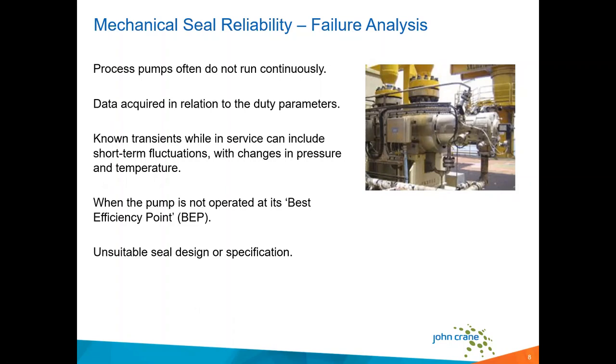Vibration is certainly a big factor when we look at mechanical seals. It can occur due to impeller wear, or operating the pump outside of optimum design efficiency, or outside of the BEP, the best efficiency point on the performance curve. Certainly this could cause problems with the seals and the bearings as well, especially if you look at the age of your equipment. If it's an older pre-eighth edition API pump, there are potentially some magnified issues with operation far left or far right of BEP in terms of hydraulically induced issues, shaft deflections and other issues. So vibration, tying back into operation of the equipment, operational data really is key in understanding the big picture here.